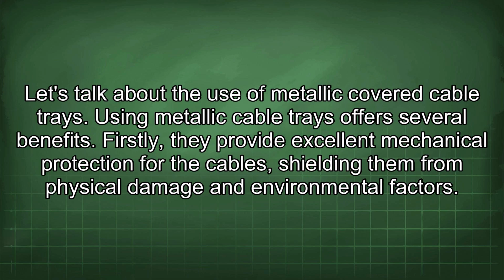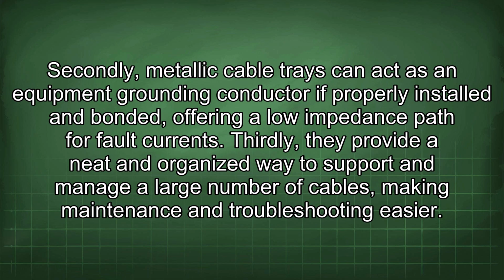Let's talk about the use of metallic covered cable trays. Using metallic cable trays offers several benefits. Firstly, they provide excellent mechanical protection for the cables, shielding them from physical damage and environmental factors. Secondly, metallic cable trays can act as an equipment grounding conductor if properly installed and bonded, offering a low impedance path for fault currents. Thirdly, they provide a neat and organized way to support and manage a large number of cables, making maintenance and troubleshooting easier.